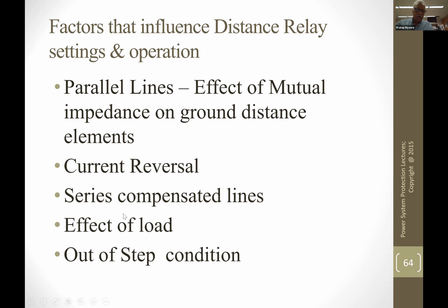Then another one is the series compensated line. Essentially, you reduce the impedance of the line by putting capacitance in series with the inductance. So essentially, you are effectively reducing the impedance. When you do this, your settings also get affected, and that is a special field, and we have to take care of that. Effect of load on the lines.